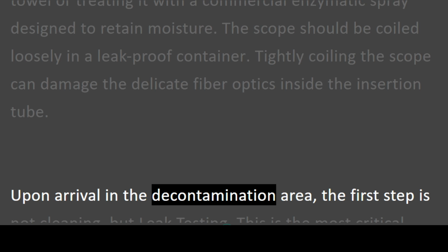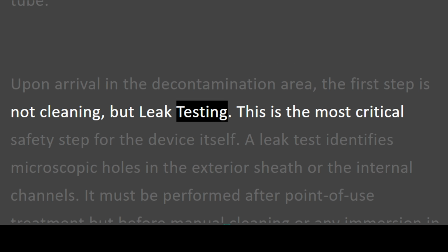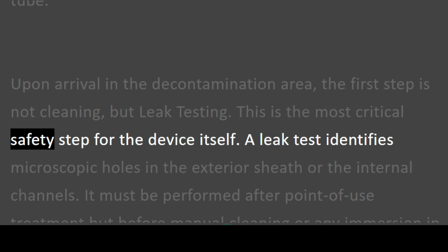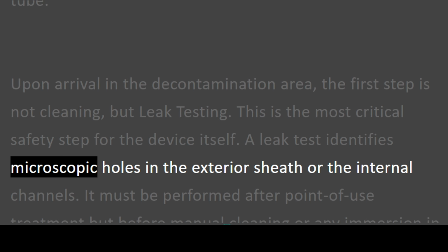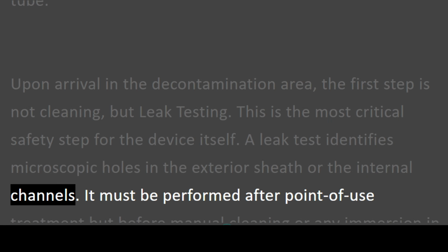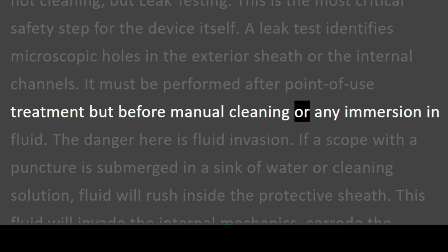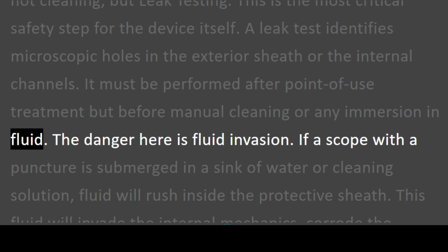Upon arrival in the decontamination area, the first step is not cleaning, but leak testing. This is the most critical safety step for the device itself. A leak test identifies microscopic holes in the exterior sheath or the internal channels. It must be performed after point-of-use treatment but before manual cleaning or any immersion in fluid. The danger here is fluid invasion.